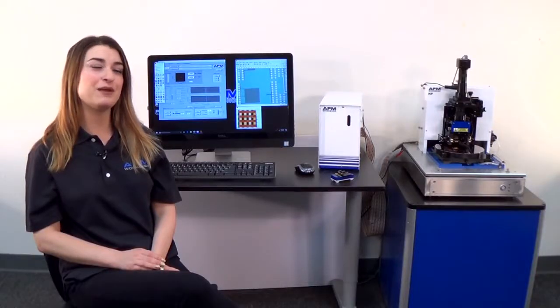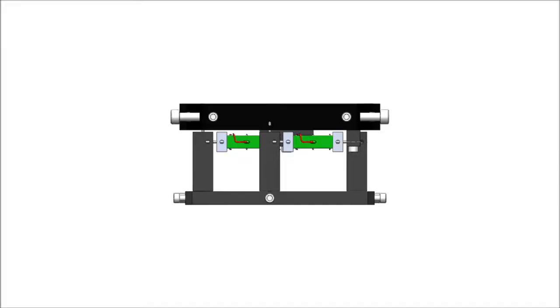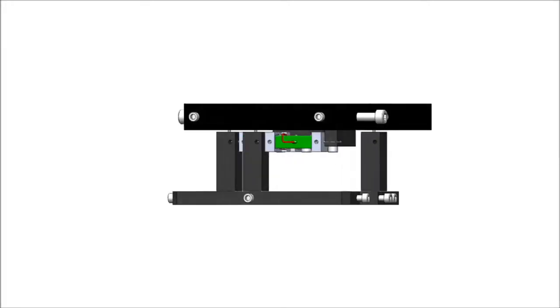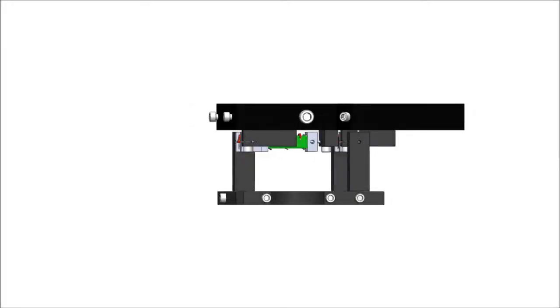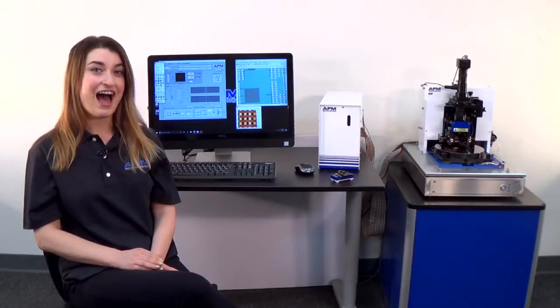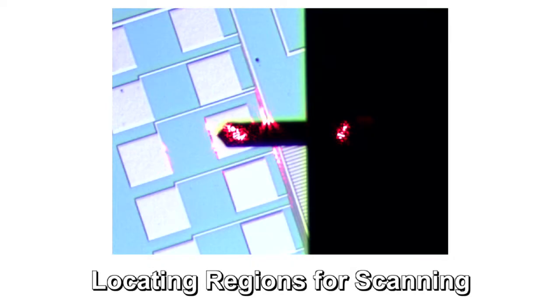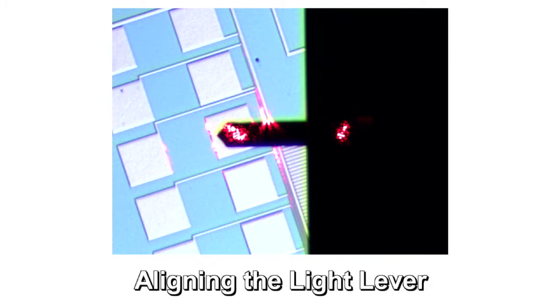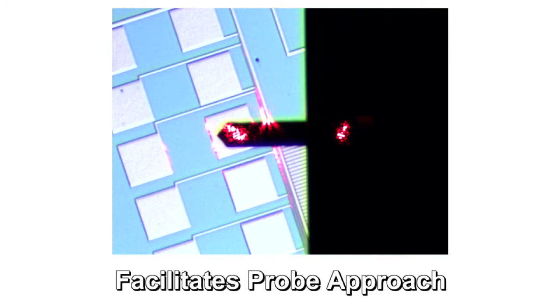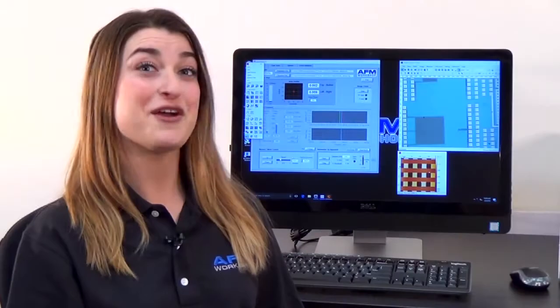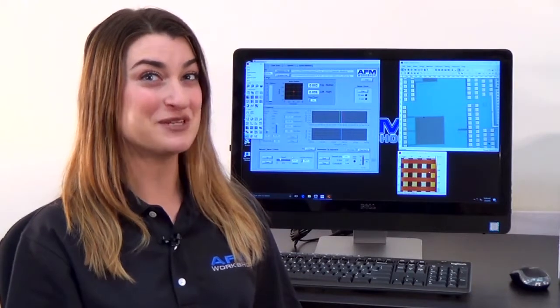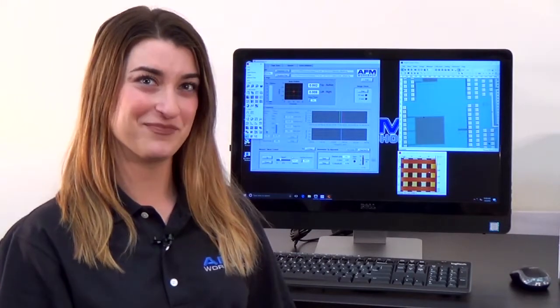A parallel plate modified tripod scanner gives AFM scans of samples with minimum bow. This feature is very helpful for metrology applications. The high-resolution video optical microscope with mechanical zoom is essential for locating regions for scanning, aligning the light lever, and also facilitates probe approach. There are several sample holding options available with the NP-AFM.